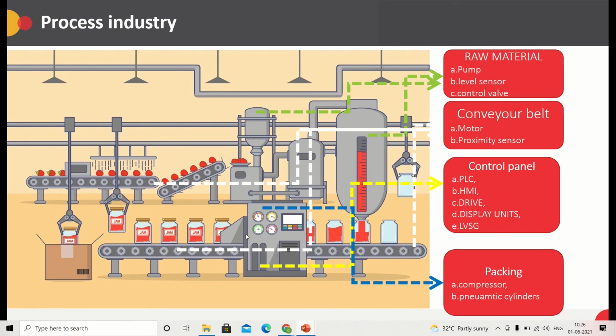Next one is the drive. What is the drive? As I told you, there is a motor here. Just imagine, when there is only one strawberry, how much speed should the conveyor belt run? If there are thousands of strawberries on the conveyor belt, how much speed does it have to run? The conveyor belt doesn't know how many strawberries are on top of it. So automatically, how will the speed be adjusted accordingly? For example, if the conveyor belt is running at 100 RPM, whether strawberries are coming or not coming, it doesn't care, it will run at the same speed. Such things you can manage only with this drive. So there are 4 conveyor belts, I mean there are four motors, and 4 drives.